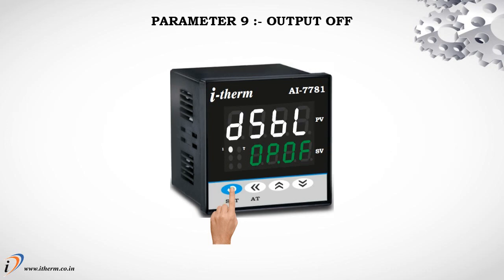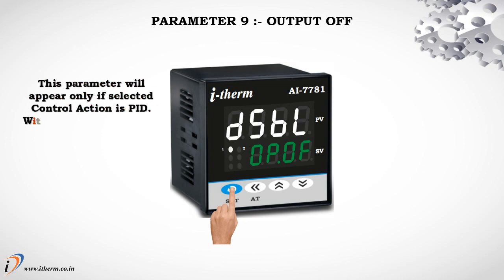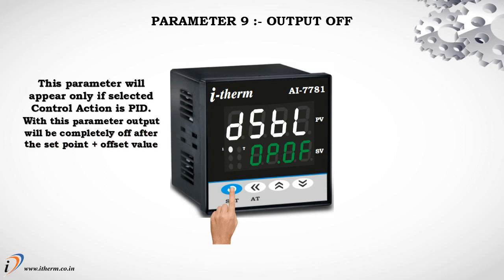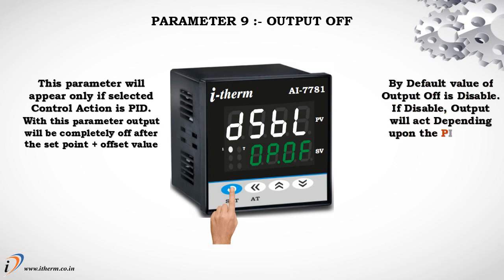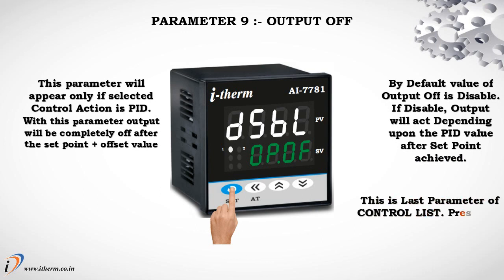Parameter 9 is Output Off. This parameter will appear only if the selected control action is PID. With this parameter, the output will be completely OFF after the set point plus offset value is reached. By default, Output Off is disabled. If disabled, the output will act depending upon the PID value after the set point is achieved. This is the last parameter of the control list. Press the Set key to enter in run mode.